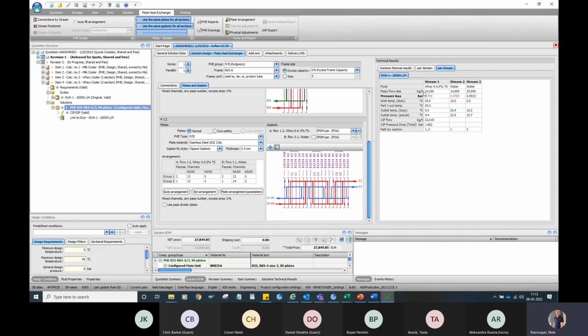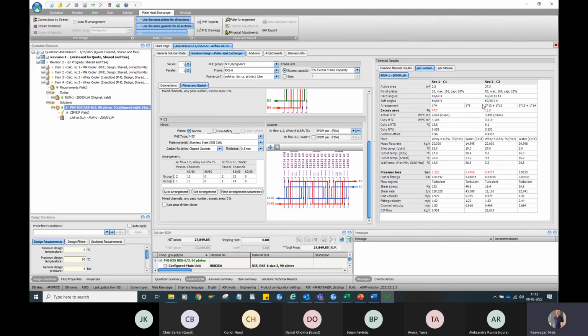If we want to decrease this to a 1 point decrease, down to 1.5, what can we do? We can add more channels here, but we can also add more channels there. But we already have a high, and also in this section is where we have the big pressure drop, you see? The problem is we have a lot of excess area here. So in real life, this one would be able to cool this down to 25 with this amount of channels.